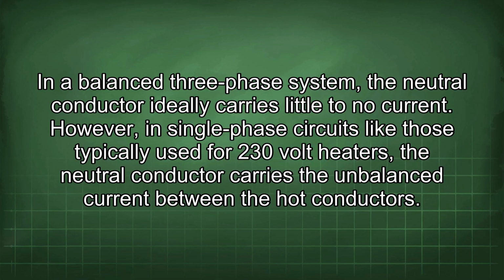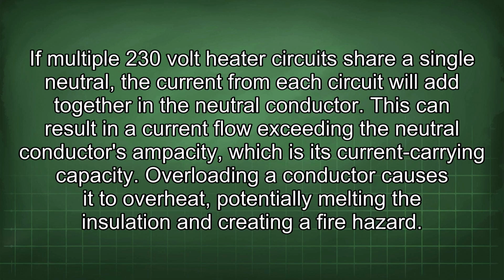hot conductors. If multiple 230-volt heater circuits share a single neutral, the current from each circuit will add together in the neutral conductor. This can result in a current flow exceeding the neutral conductor's ampacity, which is its current carrying capacity. Overloading a conductor causes it to overheat, potentially melting the insulation and creating a fire hazard.